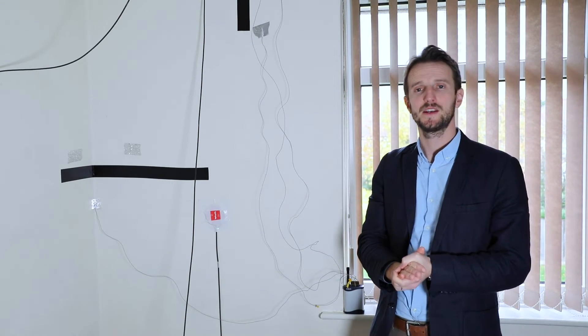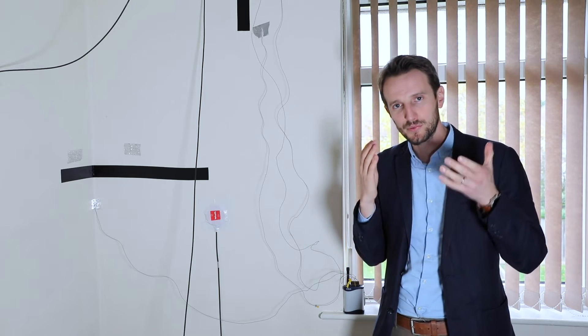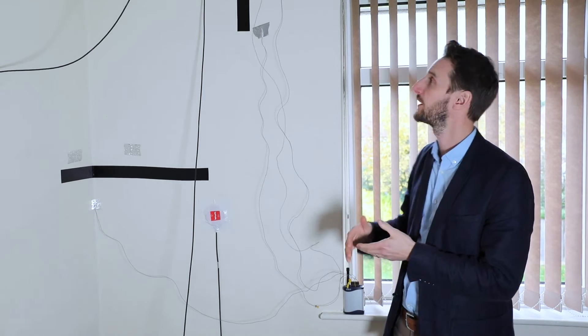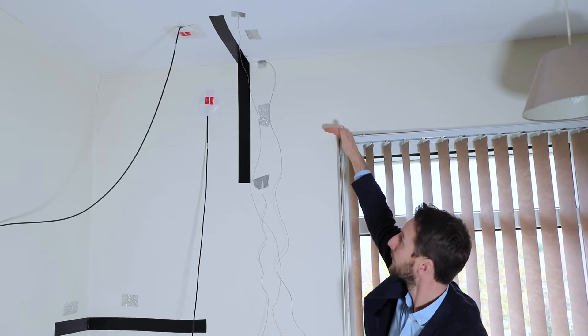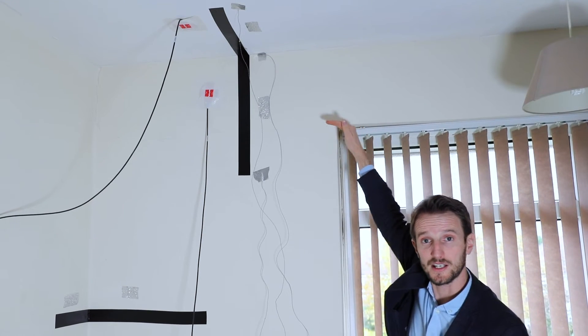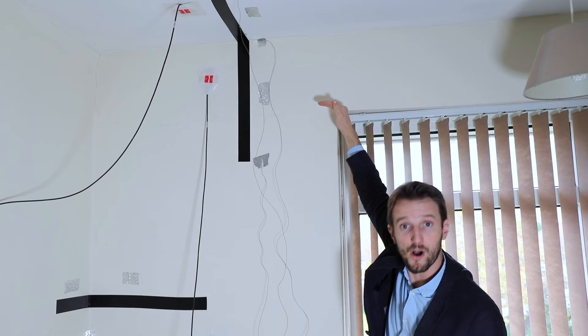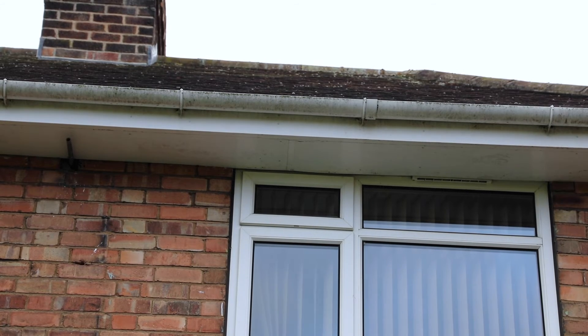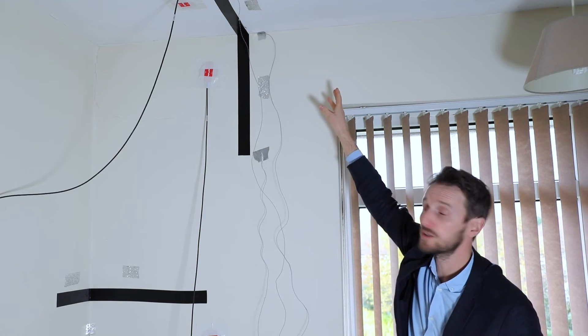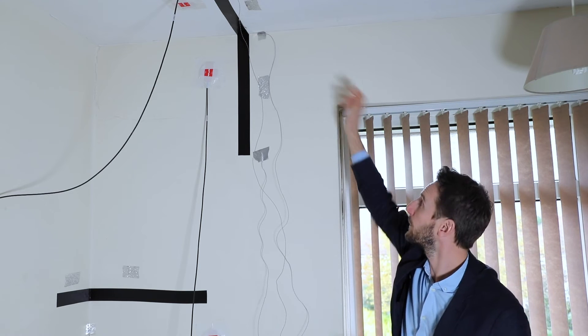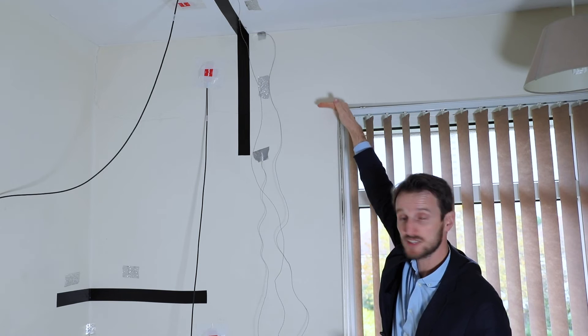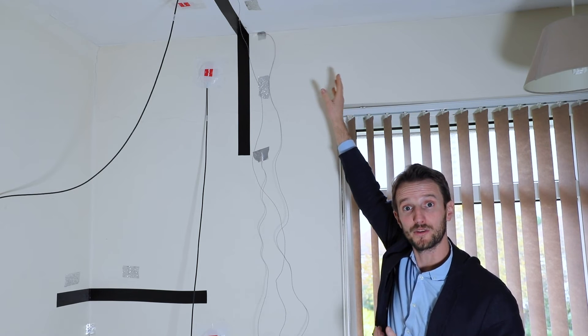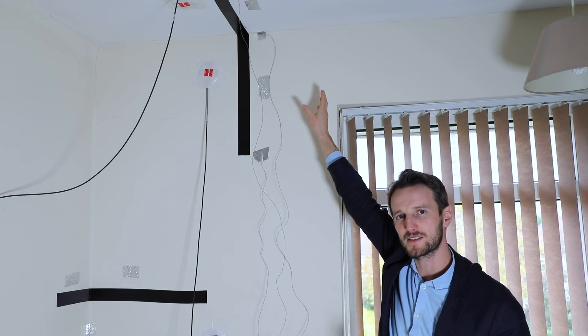Externally insulating homes is a really good way to retrofit them to improve their energy efficiency, but there are some problems and a good example is one we're investigating here. The eaves of the building are around this level and externally if the insulation was to stop here we might have a problem at the top with cold surface temperatures. We're investigating the temperatures achieved right now uninsulated, what we would achieve when insulated to here, and then if we extend the insulation up through the soffit to make sure there are no cold surfaces — we'll do those tests a bit later on.